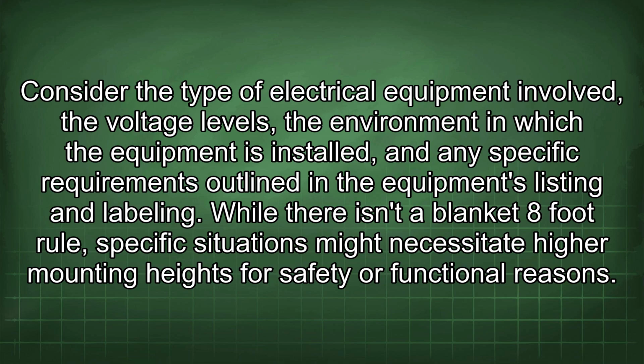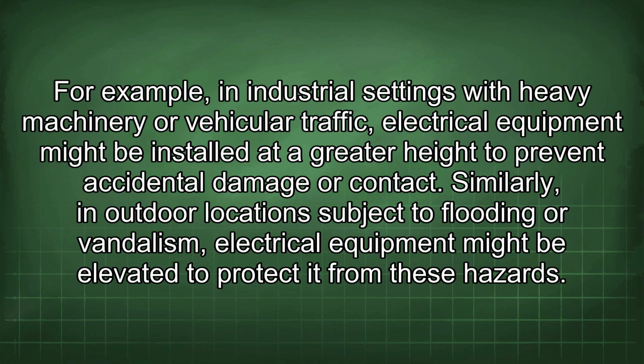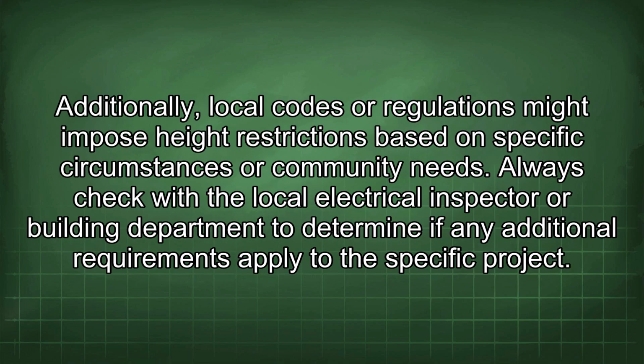While there isn't a blanket 8-foot rule, specific situations might necessitate high mounting heights for safety or functional reasons. For example, in industrial settings with heavy machinery or vehicular traffic, electrical equipment might be installed at a greater height to prevent accidental damage or contact. Similarly, in outdoor locations subject to flooding or vandalism, electrical equipment might be elevated to protect it from these hazards. Additionally, local codes or regulations might impose height restrictions based on specific circumstances or community need. Always check with the local electrical inspector or building department to determine if any additional requirements apply to the specific project.